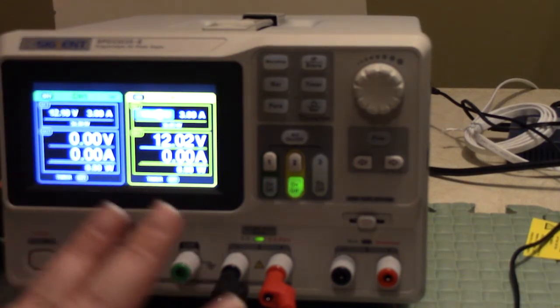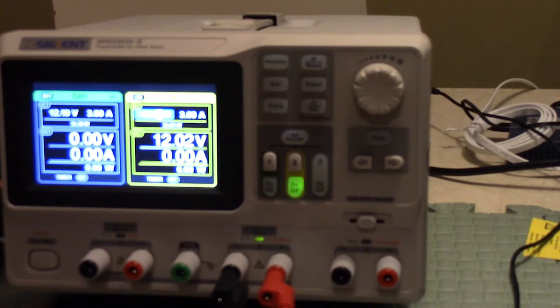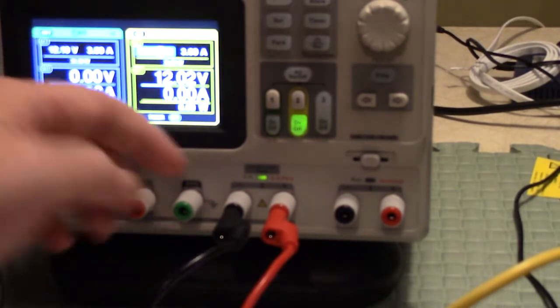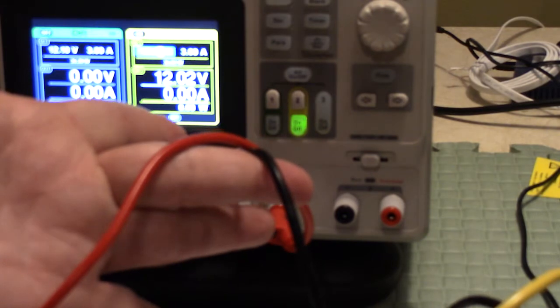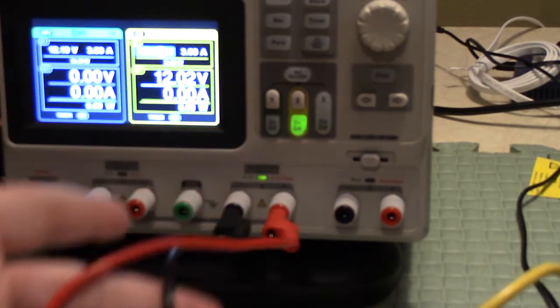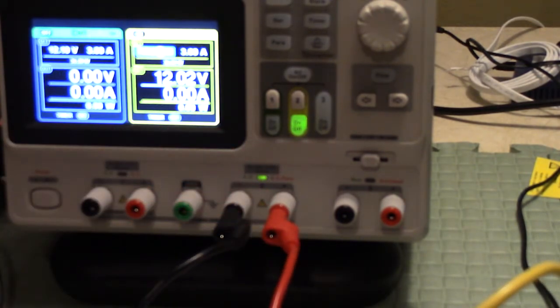Another problem with trying to use a device like this as a precision voltage reference if you're going to draw a serious amount of current: these readback values are only at the terminal, so if you have to draw current over leads like this you could have a voltage drop across the leads. Just be aware of that if you're going to use it as a precision voltage reference and you're going to draw a significant amount of current from it.